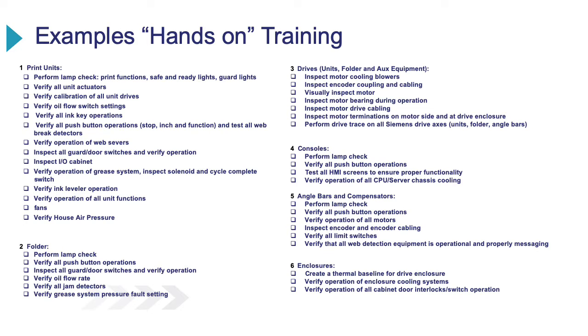A checklist as displayed is a good tool to develop a preventive maintenance program, refresh your memory, or to train new technicians. A high-level list can verify each system function, and a lower-level list can address more specific components such as direct I/O, overload settings, and safety switches. This example would be part of the hands-on training where the student could check off items when complete verification of each system is completed. Designing a specific list for your equipment is time well spent.